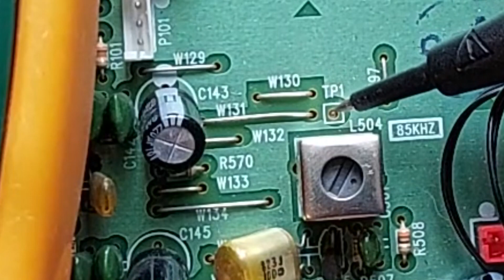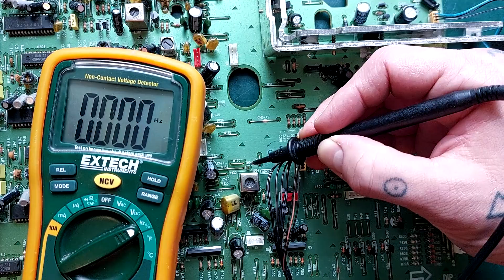That stands for test point, and that's the test point for this, which is where I'd put the positive pin, but you can see it's empty - it's broken off. These two jumper wires go to it though, so I can put the red pin there instead, and the black one there. It's reading 60 hertz or so, that's just hum, but once I connect it properly - there we go, 84.64 kilohertz. It's meant to be 85 kilohertz.